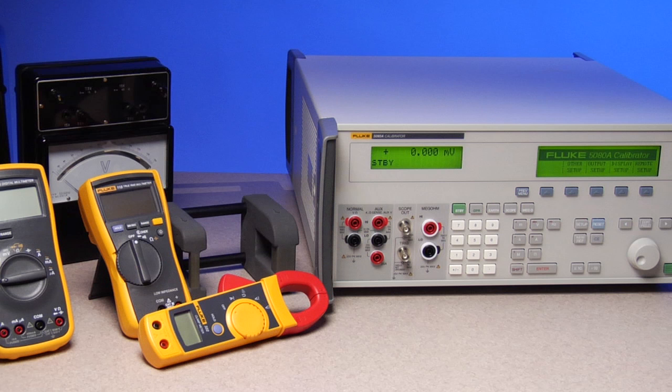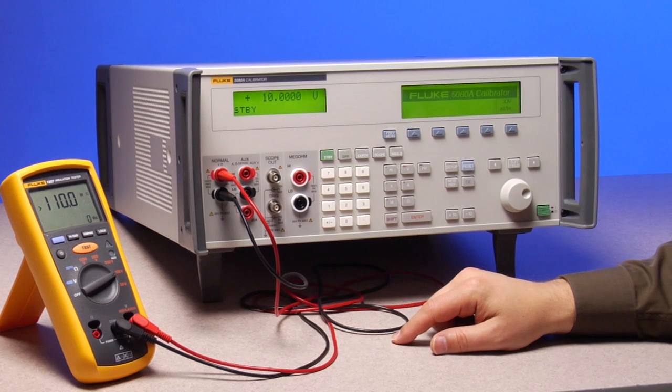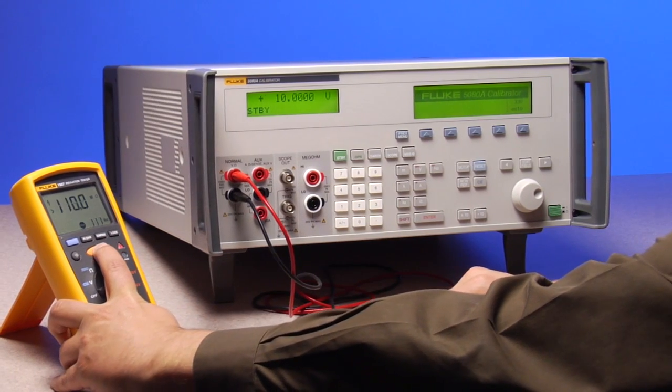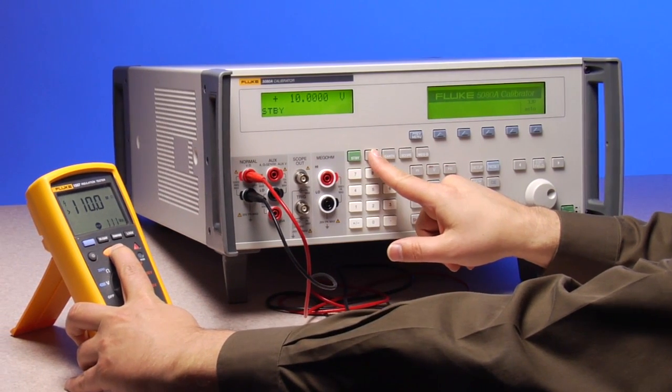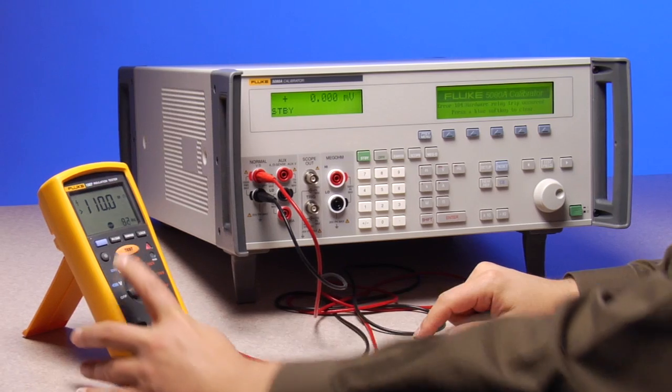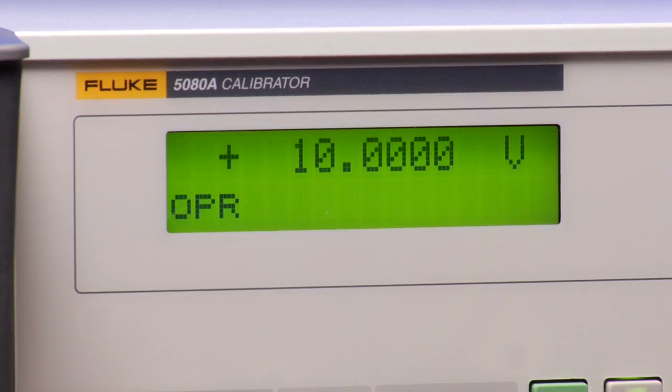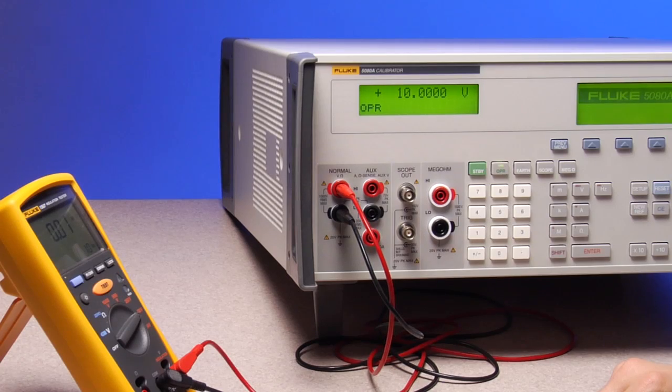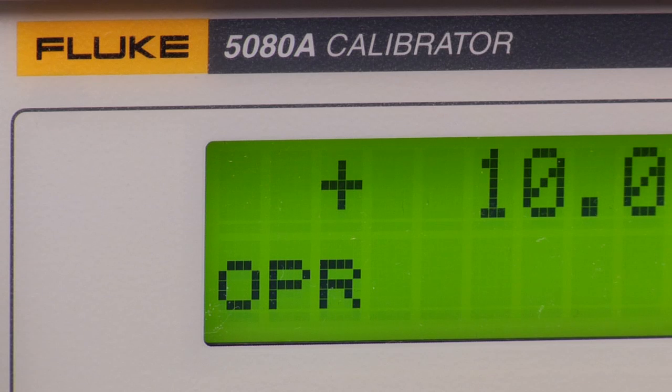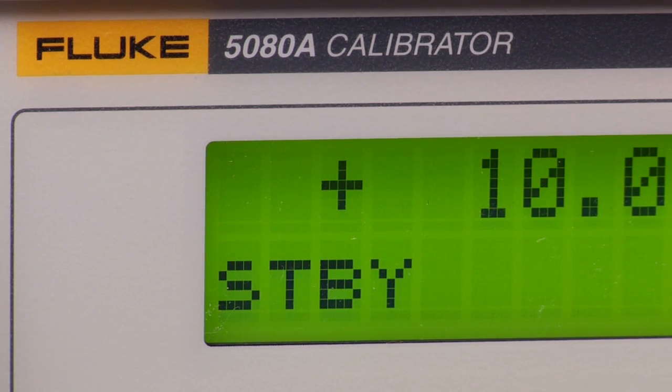This calibrator has innovative protection circuitry that prevents it from being damaged by reverse input voltage. Under standby mode the 5080A checks for harmful voltage before it changes to operating mode. Under operating mode the 5080A immediately detects harmful voltage at output terminals and automatically goes into standby.